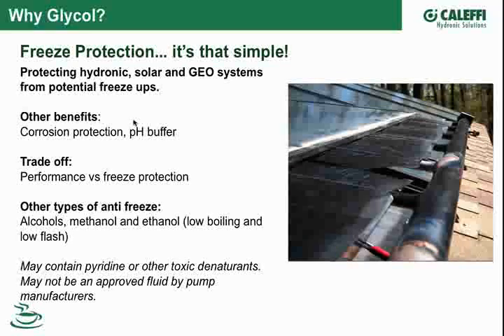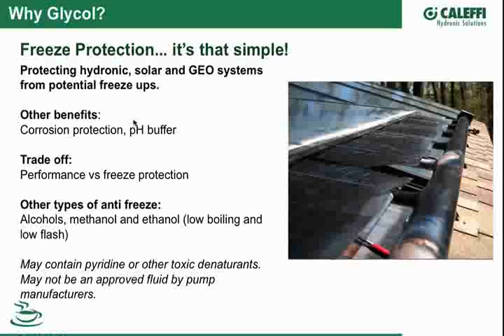We talked a little bit about the alcohols. The other thing I learned recently from one of the pump manufacturers is that none of the pumps they manufacture has ever been approved to pump a flammable liquid, which is what the methanols and ethanols sometimes used in geosystems are. So just putting the pump into that application, I don't know if I'd say you're voiding the warranty, but you're using it for an application that's never been tested or approved for. Just keep that in mind too.